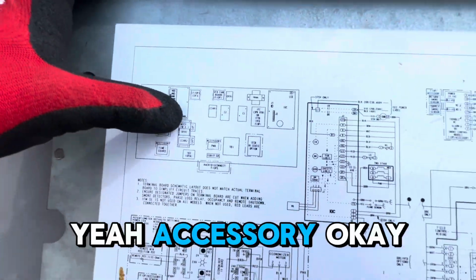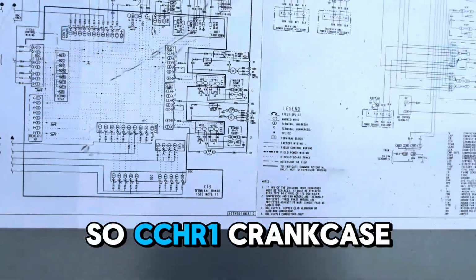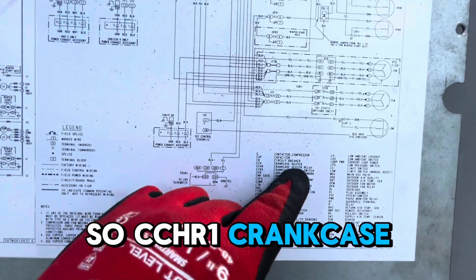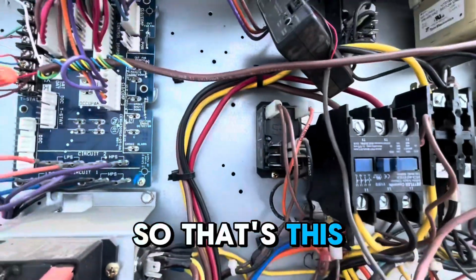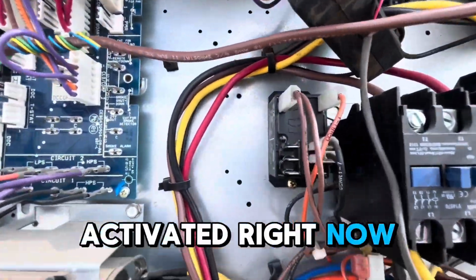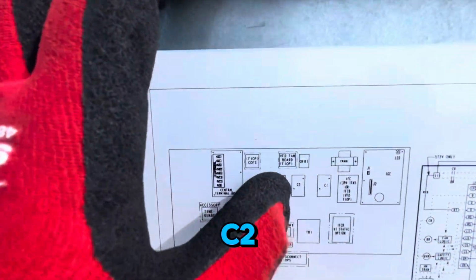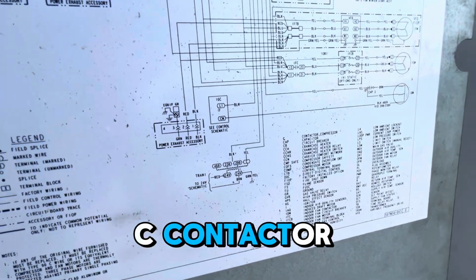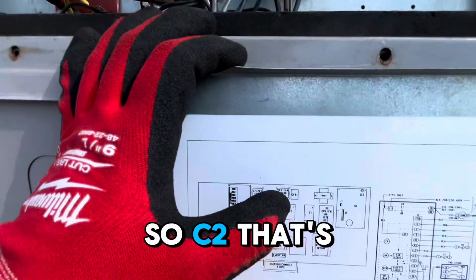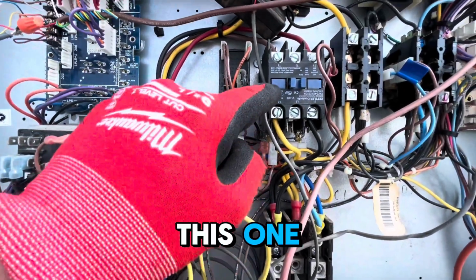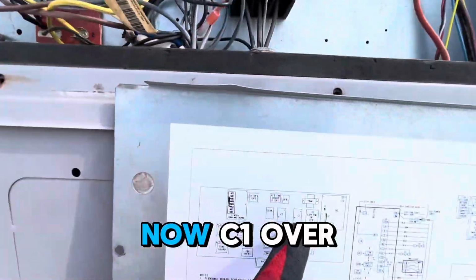Oh yeah, accessory. Okay, so CCHR1, crankcase heater relay. Okay, so that's this one. That's not activated right now, so that's good. C2, contactor compressor. Okay, so C2, that's this one. Circuit 2 is not on right now.